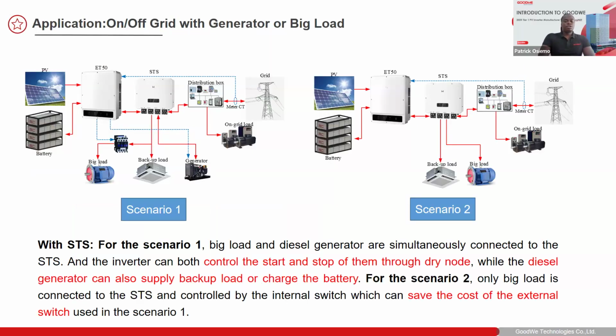If you're doing an installation with the 50 kilowatt hybrid, these are some of the scenarios that you can use. In the first scenario, in case you have a diesel generator, and the system is off-grid and the battery is low, then the inverter can send a start signal to your generator. So that's the first option. In case you don't have a diesel generator but you do have a very big load, then the same generator port can be customizably configured to be a big load and output to a load.